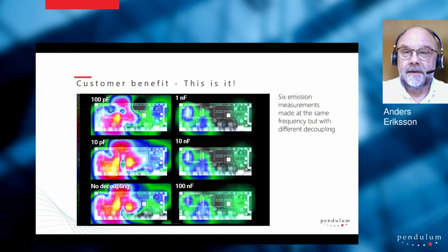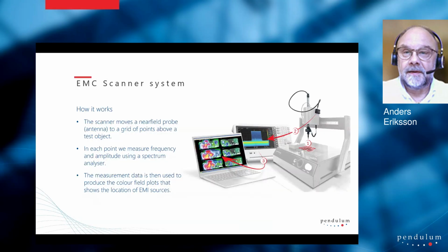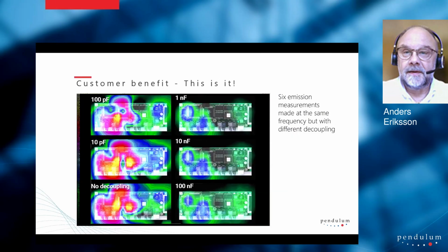Because this is actually what we do. It's a probe and a spectrum analyzer. People have been using this kind of probes and spectrum analyzers for like 50 years to hand sniff to find sources, and it works. You can find a source using just a spectrum analyzer and a handheld probe, but the problem comes when you try to repeat the measurement. That's where we need the scanner to make it repeatable, and the software to document and to visualize. But this is the thing: objective, comparable measurements.